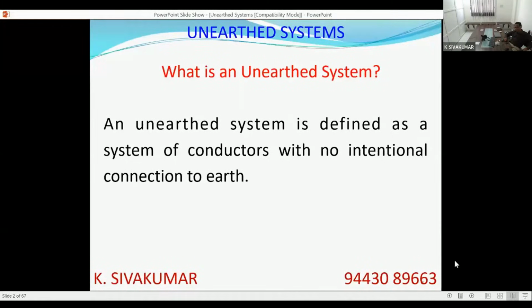So generally the scheme will be something like this. There will be a source, maybe a transformer or a generator, a 3-phase 4-wire system or 3-phase 3-wire system, with a distributed neutral or without a distributed neutral. The neutral, as you can see, is not earthed anywhere in the network. A typical scheme will be like this. So an unearthed system is a system in which there is no intentional connection to earth. As you are aware, in an earthed system, we intentionally connect the neutral to earth. In an unearthed system, it is not done.